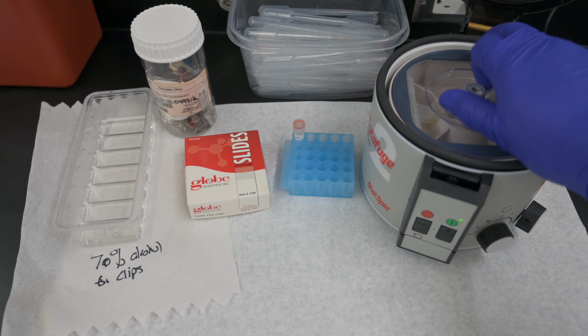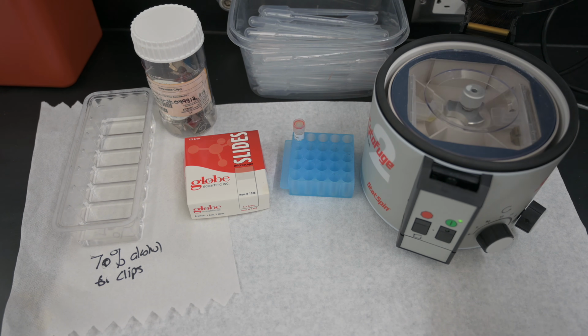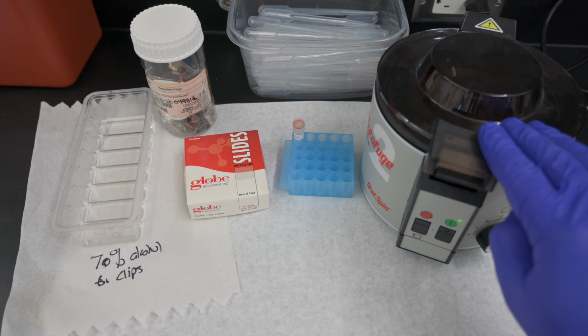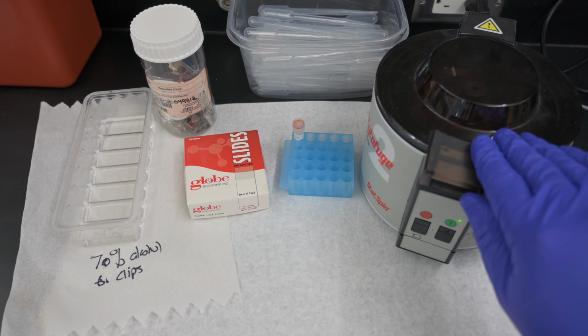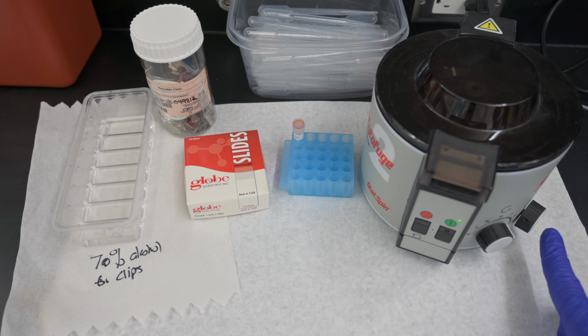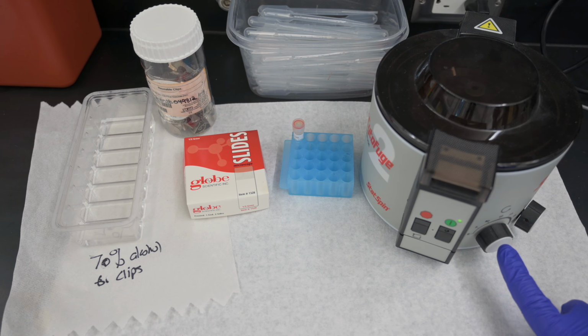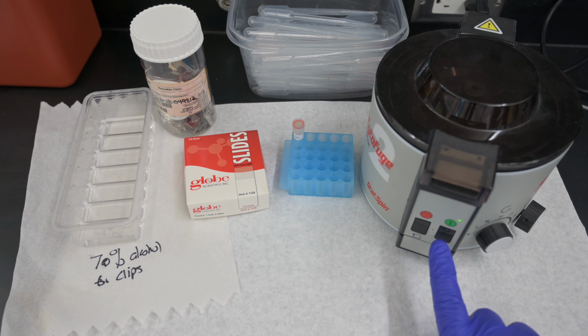And then we're going to close the lid on the cytocentrifuge until we hear the lock engage. The dials on the side here, this is where you can adjust your RPM as well as time. According to the SOP, we're spinning this at 1600 RPM for 4 minutes, and then we're going to hit that start button and allow the sample to centrifuge.